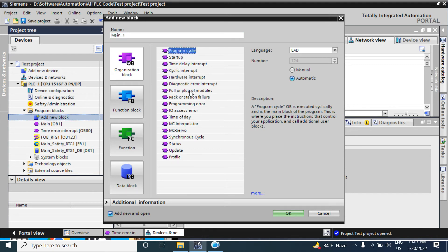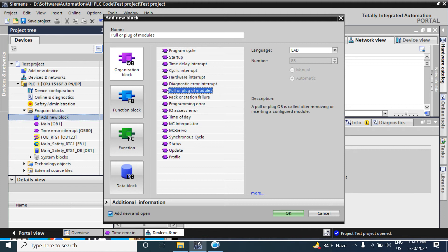Another OB is Pull or Plug Module. This OB is called after removing or inserting a module — whether in a distributed module or in a central rack. It can be called both during insertion and removal. If you do not call this OB in your user program, the CPU will not go to stop mode when you remove or insert a module — it will just ignore it.